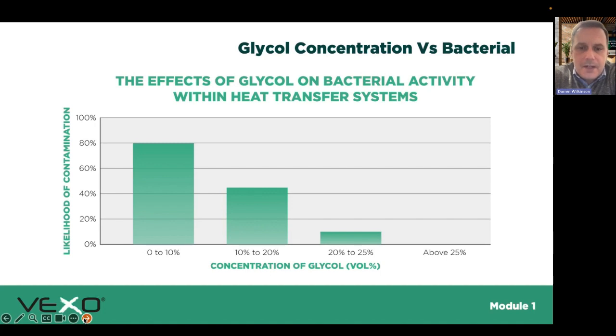But anything below that, as you can see from this graph, you start to run the risk that you're going to start feeding the bacteria. So rather than them not being able to flourish, they actually can flourish as you go to lower levels of concentration. And unfortunately, not only do they consume your glycol, they actually produce glycolic acid. So you can end up with gassing in the system, acidic pH, and a world of problems essentially. So if you are looking at a system to add glycol, the industry generally recommends you make sure it's at 25%.